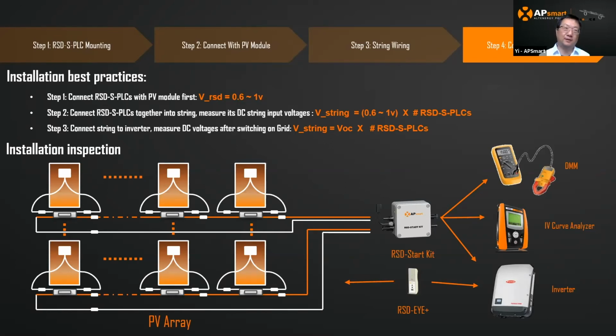All right, so after the string has been installed and is ready, some systems require, before the combination, some IV curve or measurement of the system voltage after the turnaround. So we do have two very handy tools ready for the customer. One is called RSD-Start Kit. Another one is called RSD-EYE+. The start kit function is to independently turn on your string without turning on the grid, which means if you want to do the IV curve or see exactly what voltage comes out from this string, you use this tool.